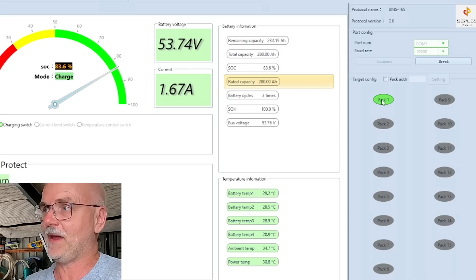Probably you can already see the problem with this design, because you have to change the dip switches all the time to get access to the configuration of the Master BMS. The other battery banks will be fine, but the Master is not accessible. So I would call this a major design flaw.